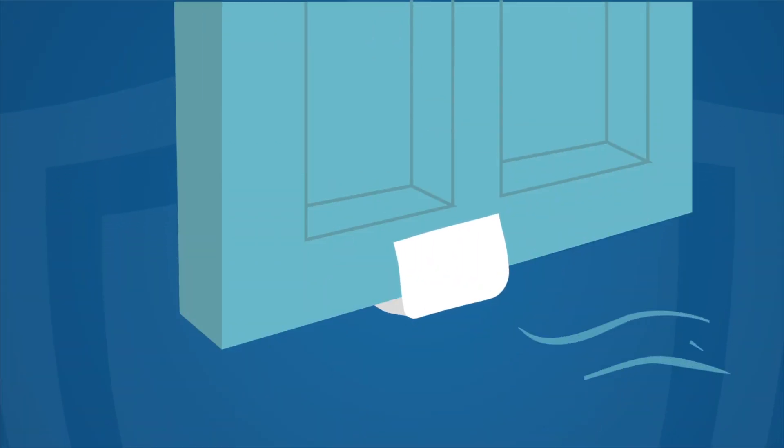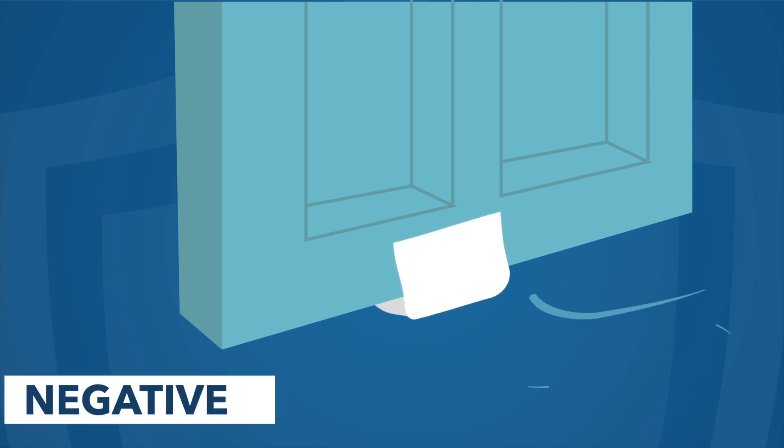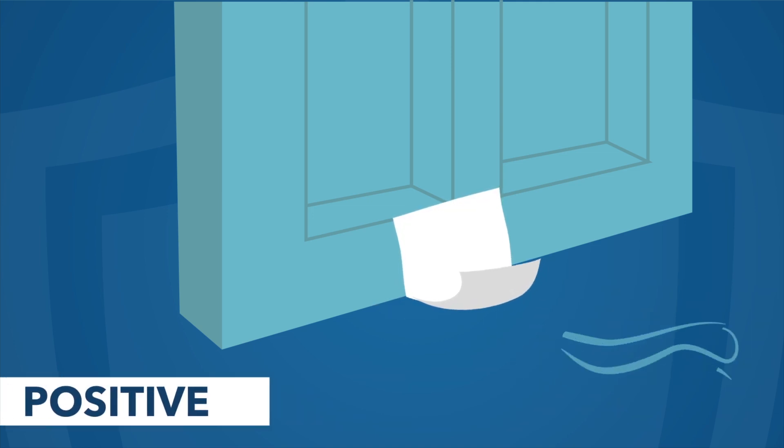If you are concerned about a room's pressure, you can quickly check to see if a room is positive or negative pressure by holding a single ply tissue or piece of toilet paper at the bottom of the closed door. If the paper is sucking in, the room is negative. If the paper is blowing out, the room is positive.